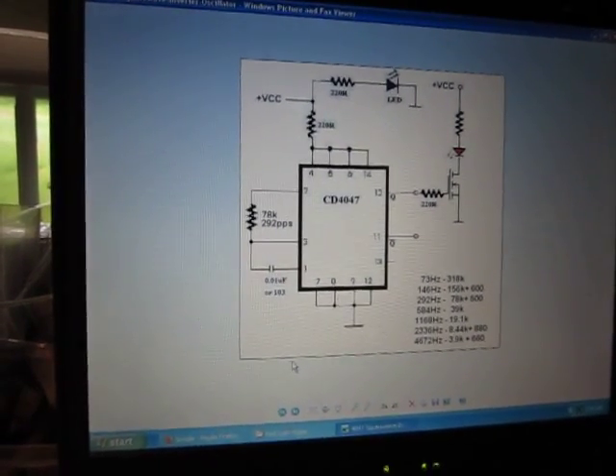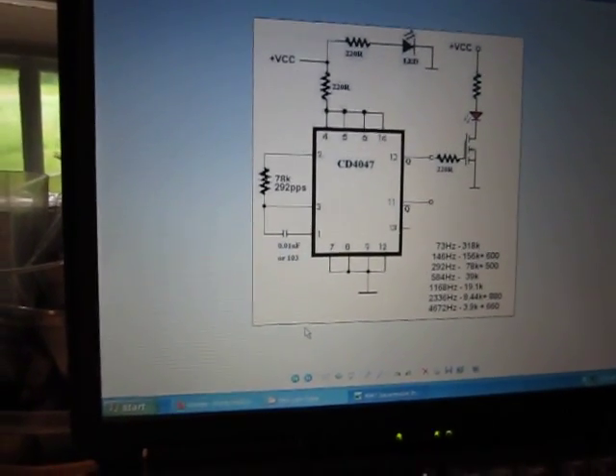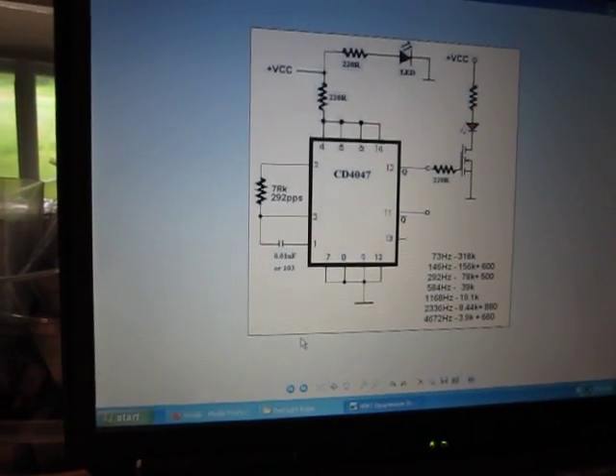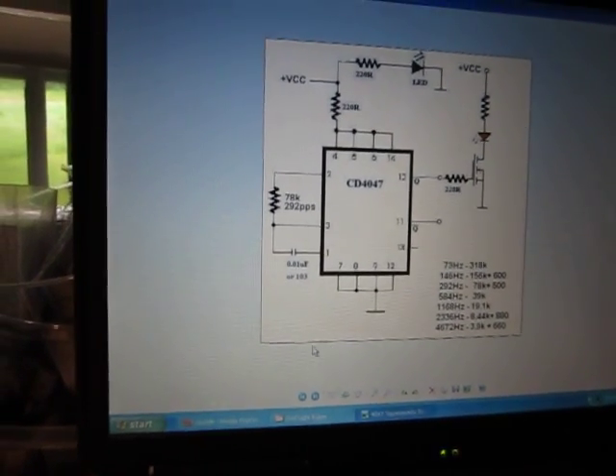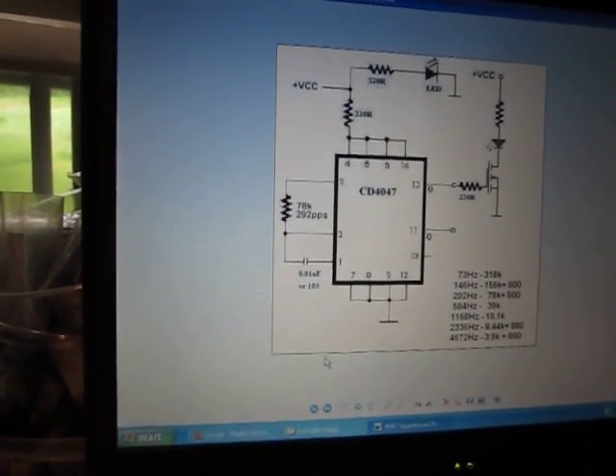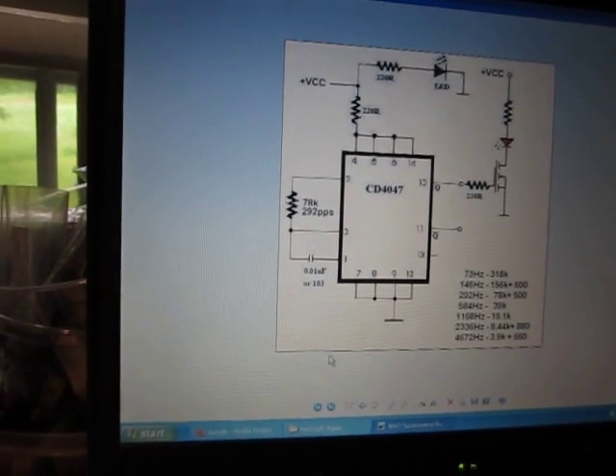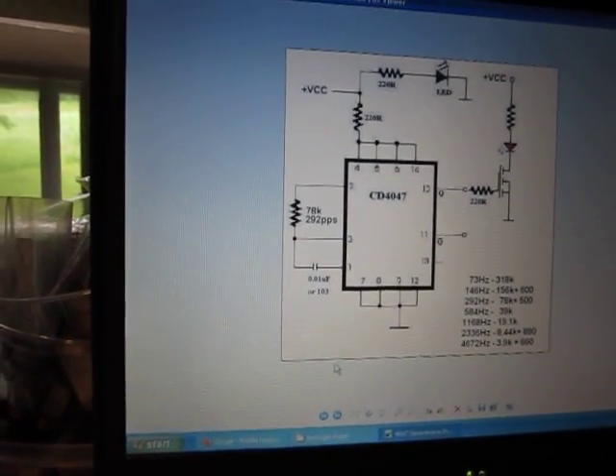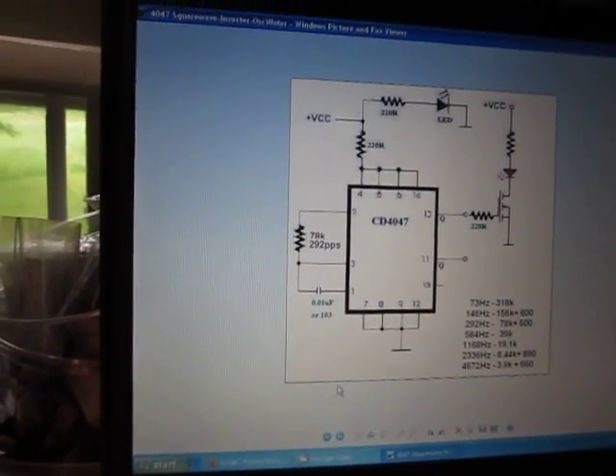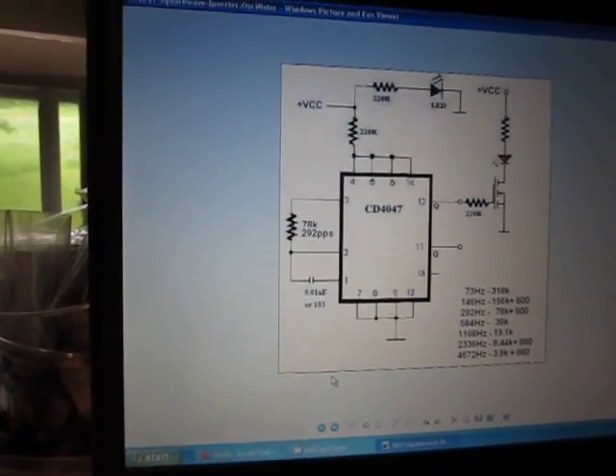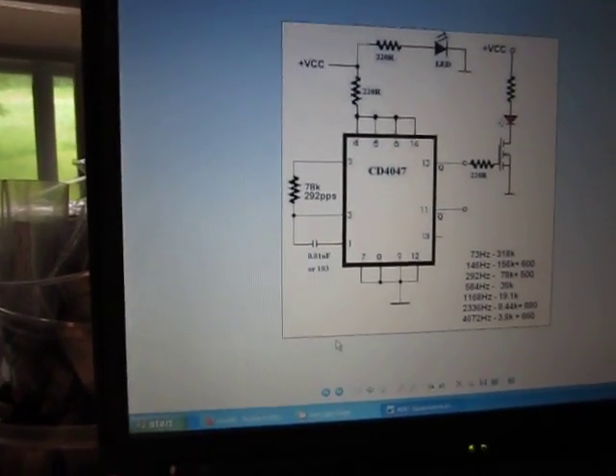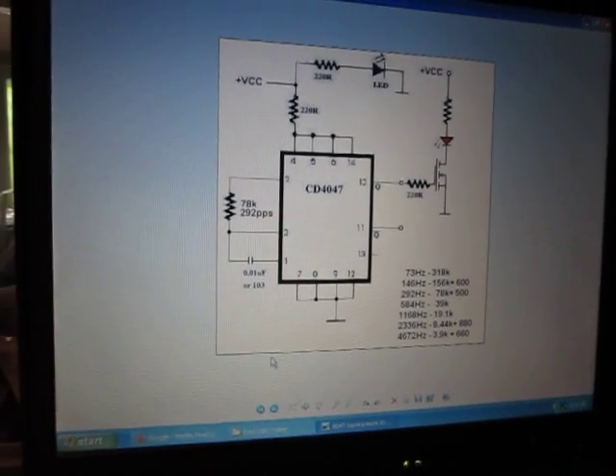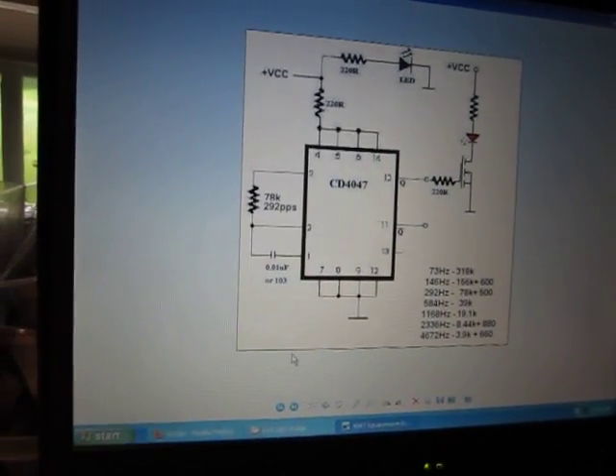These frequencies are multiples of 73 pulses per second. We have the lowest at 73, then double that at 146, then 292, 584, 1168, 2336, and 4672 being the highest. The highest is mainly for pain control and athletic conditions.